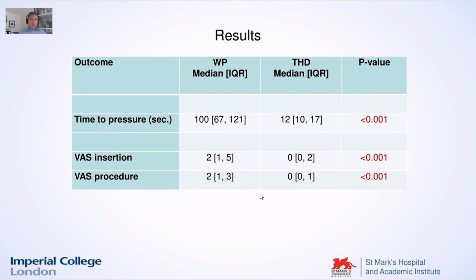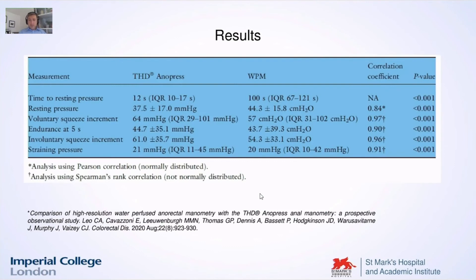So the time is much longer. On the VAS score, very similar results, but there was a statistical significance — the Anopress seems to be better tolerated. When we compare the manometric results, there was a nice correlation between the two devices, so the Anopress correlates well with water-perfused manometry.